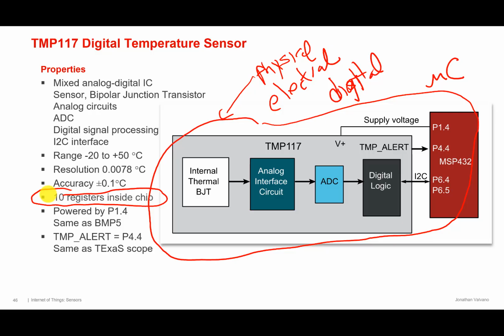They claim it's accurate. Remember, your job is to calibrate it and determine if the specification from the device is true. Remember, resolution is the smallest change I can distinguish. Notice the resolution for this is much smaller than its accuracy, because, as we saw in the last video, lots of things can affect accuracy, like drift, transducer interchangeability, and noise. Noise affects both.